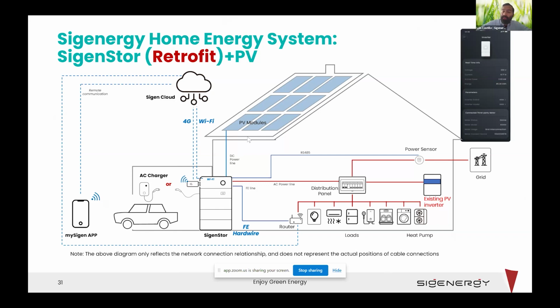What we do is detect excess power coming from the PV inverter and then charge the battery if there is storage capacity available. So you don't need to touch or rewire anything on your existing installation. The only additional component, and it's optional, is an additional pair of CT power sensors that you can connect at the output of the existing inverter, only if you want to see those parameters on our app - the output values of current, voltage, and power. Otherwise, that additional power sensor is not necessary.